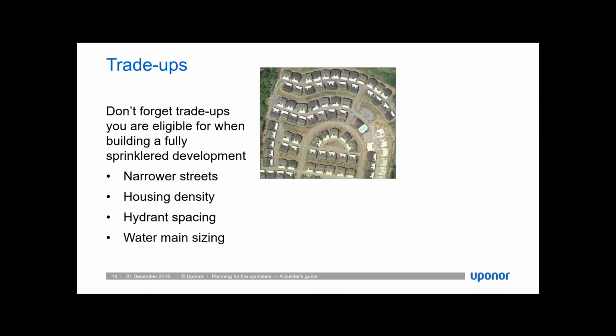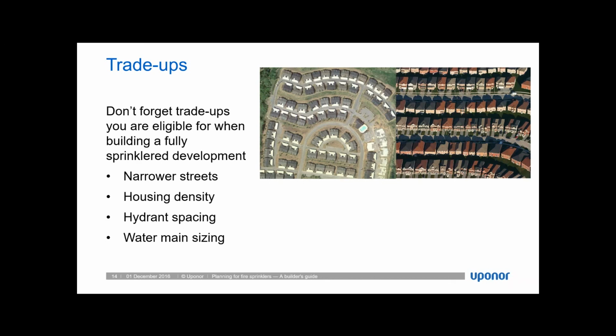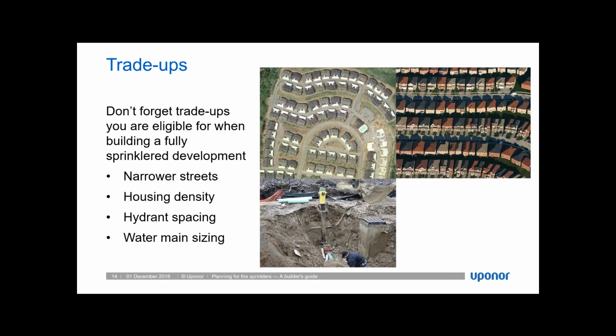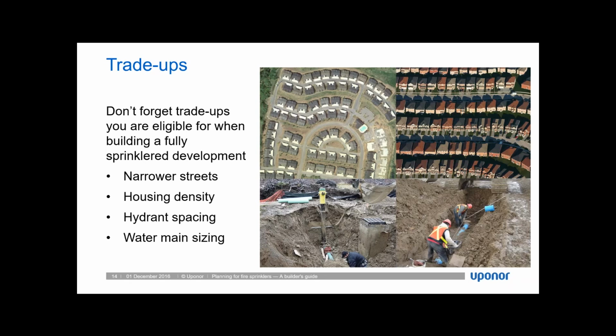Some of these are going to be the option to have narrower streets, higher housing density. You can have larger spacing between your fire hydrants, and you're going to be able to possibly have reduced water main sizing. The thinking is that when you have a fully sprinklered development, it's not as important to worry about access for fire trucks, accessibility of the fire hydrants to the firefighters when they arrive on scene. There's not as much of a concern for exposure to neighboring homes, and the water mains may not need to be sized large enough to handle a fully involved house fire, since the fire would presumably be controlled very early when it is very small by a smaller amount of water that is provided by a residential sprinkler system.